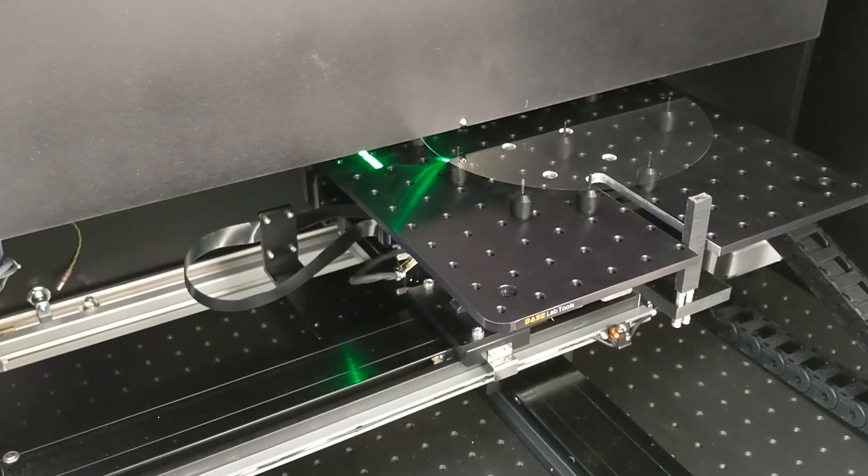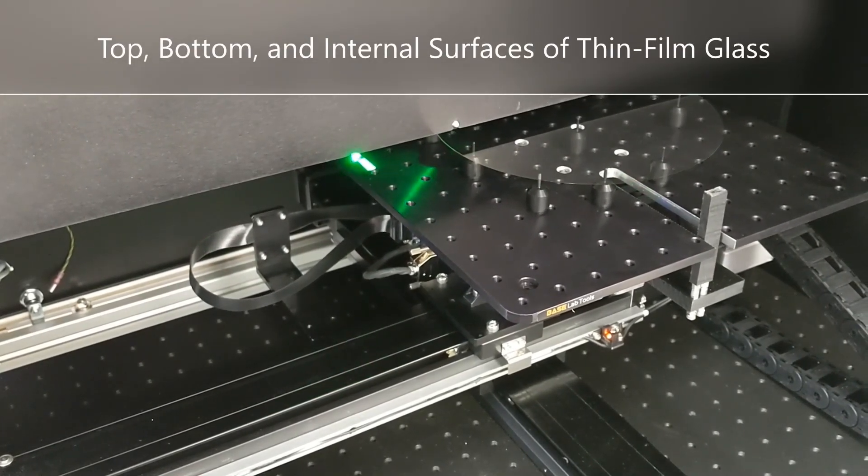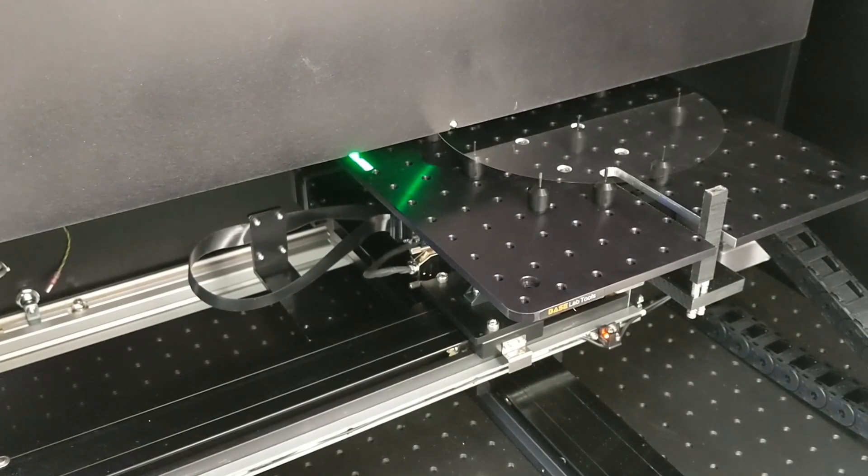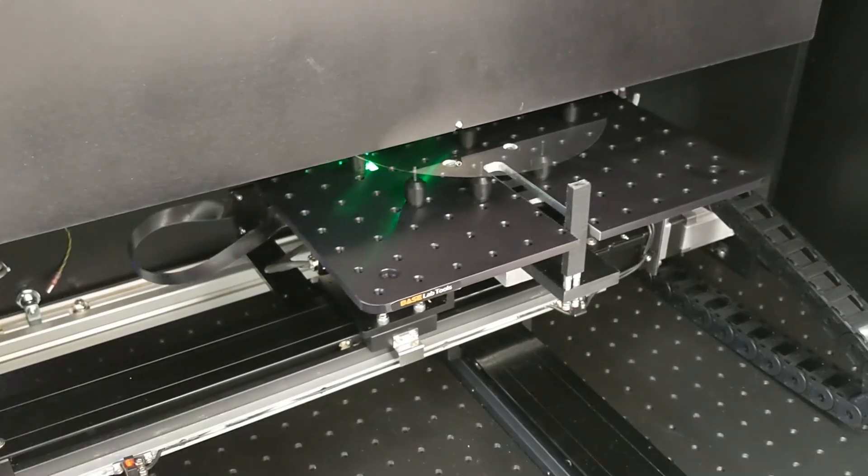Unlike other instruments, the AT1 optical scanner can scan the top, bottom, and internal surfaces of thin film glass, making it one of the only machines capable of detecting inclusions.